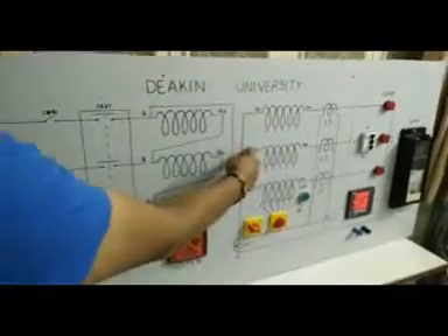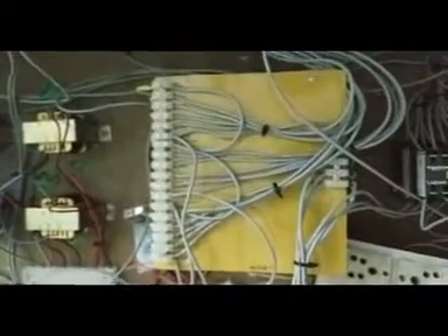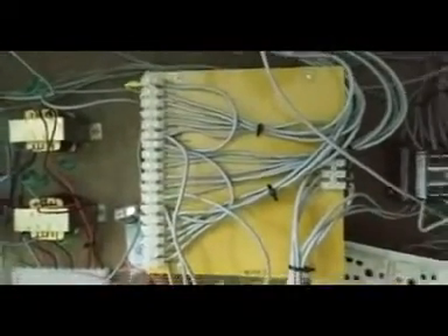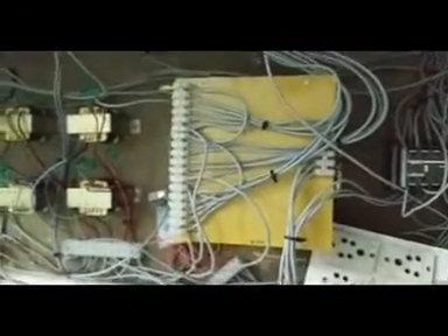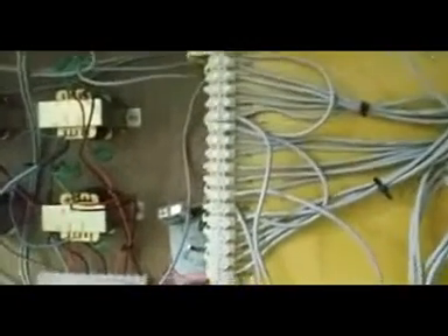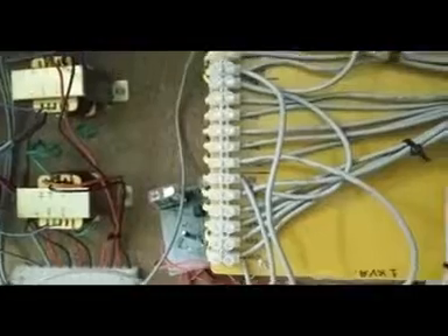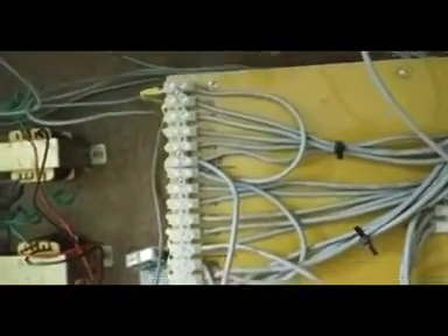I will show all these components, the phase selector switch and the tapping selector switch, at the back of the panel. So this is the main transformer with tapping on the secondary. This is the secondary, and you can see the tappings, which are 5%, 10%, 30%, and 100%. The next is the current transformer.